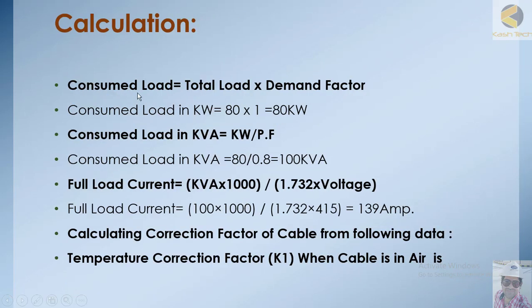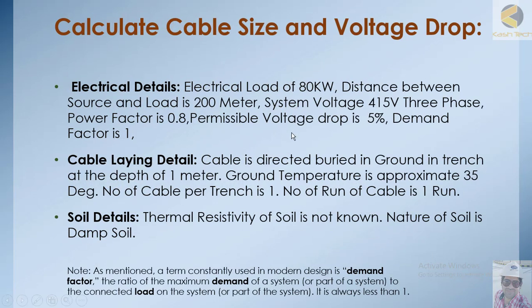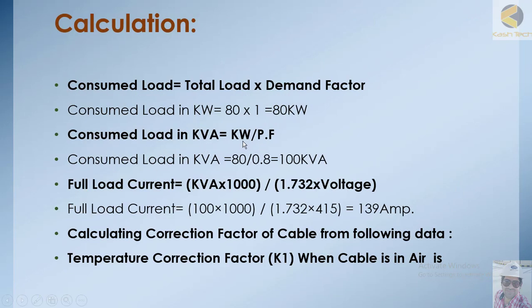Now we start the calculations. Consumed load equals total load multiplied by demand factor. So consumed load equals 80 into 1, which is 80 kilowatt. Consumed load in kVA equals kilowatt divided by power factor, which gives 100 kVA. Full load current equals kVA into 1000 divided by root 3 into voltage.